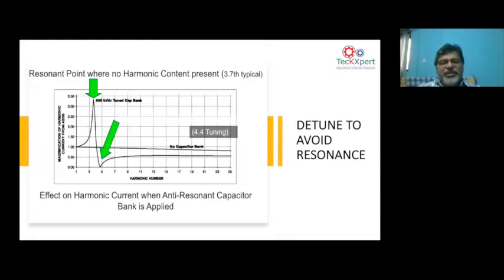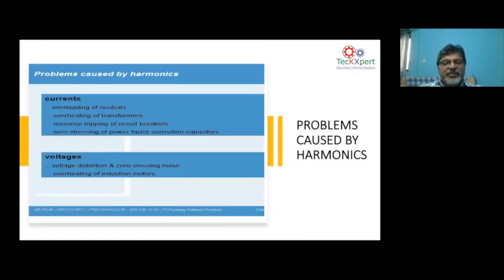Again, the same one, detuning. When you put a 500 kVAR capacitor bank, you detune it, you're shifting the frequency between the third and fifth and trying to protect the capacitor bank. That is what detuned means, to avoid resonance. Yeah, go to the next.